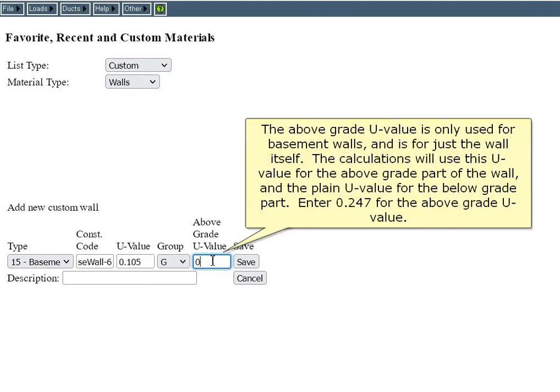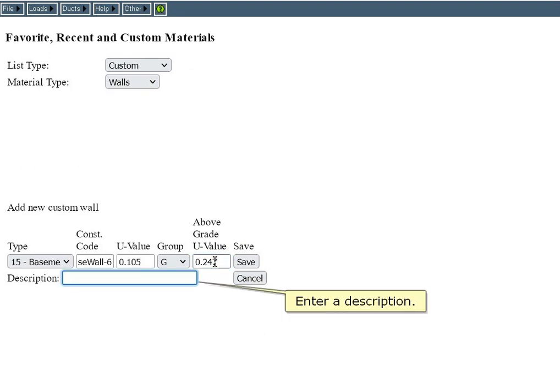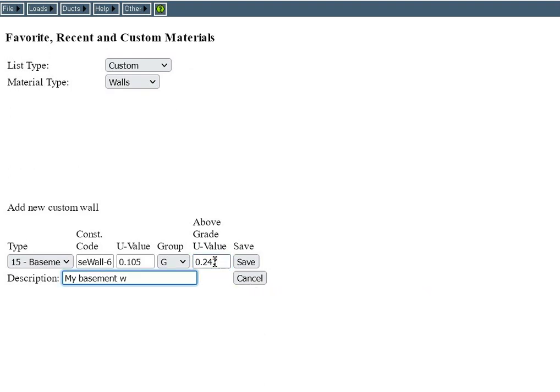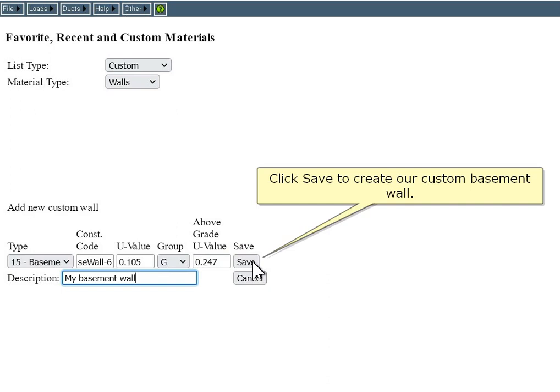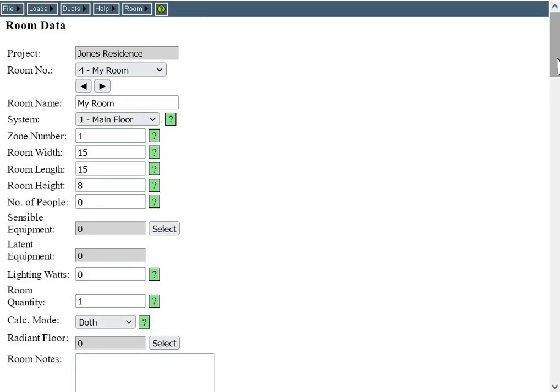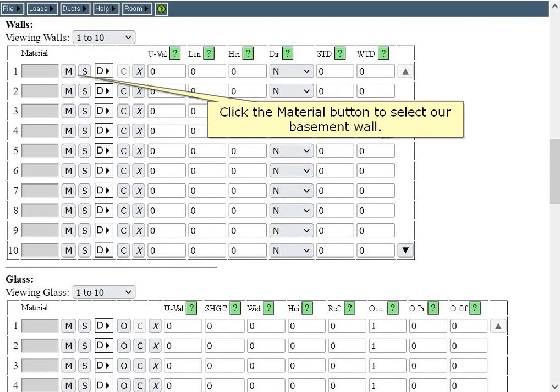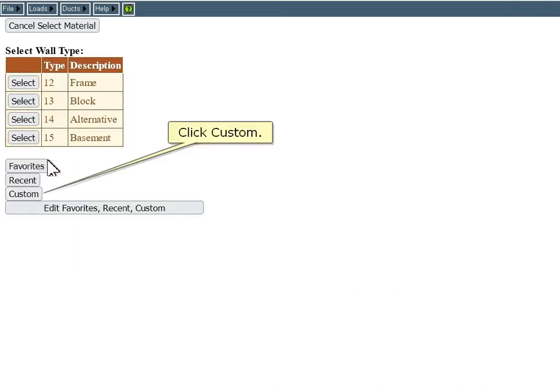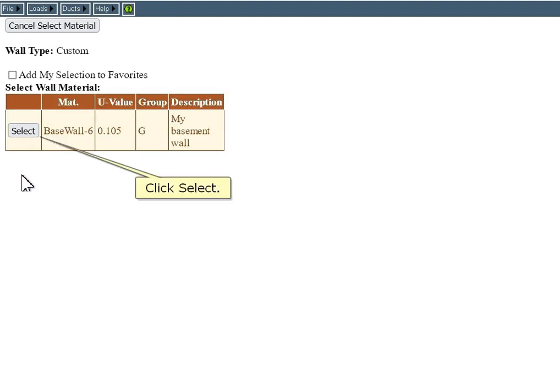The above-grade U-value is only used for basement walls and is for just the wall itself. The calculations will use this U-value for the above-grade part of the wall and the plain U-value for the below-grade part. Enter 0.247 for the above-grade U-value. Enter a description, then click Save to create our custom basement wall. Let's return to the room data window and add our new custom basement wall to the current room. Click the Loads menu, then click Room Data. Click the material button to select our basement wall, click Custom, then click Select.